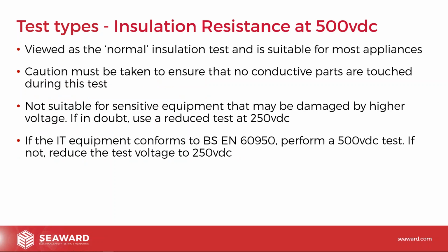The 500 volt insulation resistance test is generally seen as the standard, the normal insulation resistance test, and is suitable for most appliances. The reason I say most is because we are applying 500 volts between either the earth connection or, for class 2 equipment, exposed metal parts and the live parts within the equipment. It is possible for that to damage equipment. 99.999% of equipment is absolutely fine with a 500 volt test, but some equipment is susceptible to damage at 500 volts. The argument would always be, as we mentioned a little further down, that anything that's surge protected or sensitive, or particularly anything that's expensive, generally we'd recommend doing at 250 volts instead.